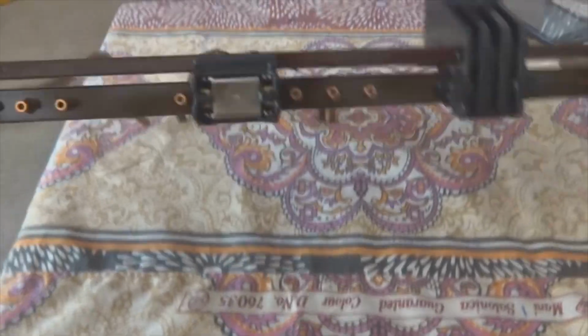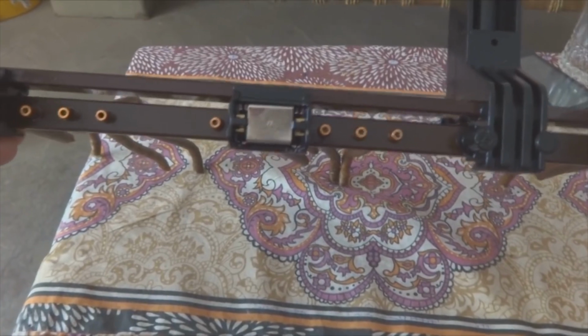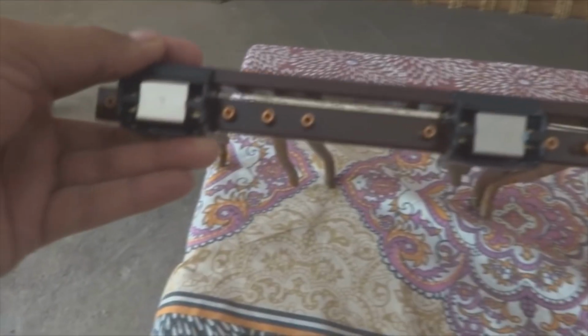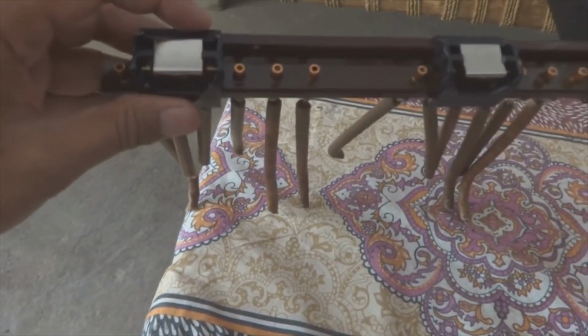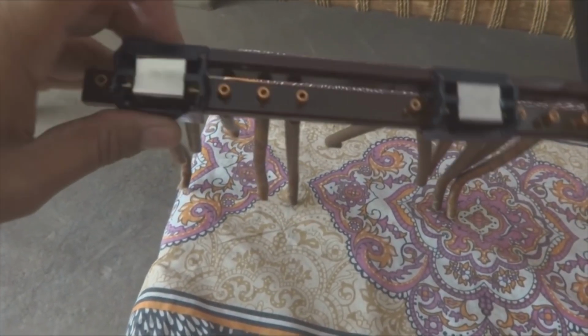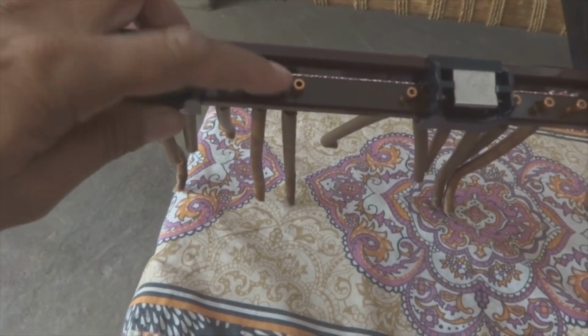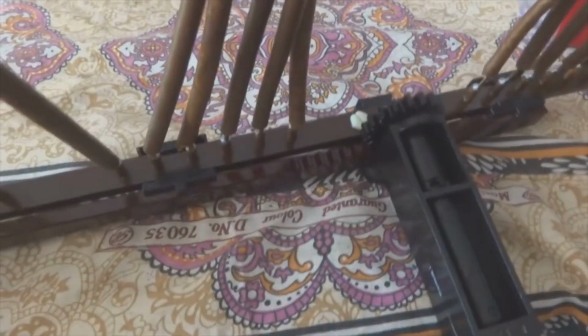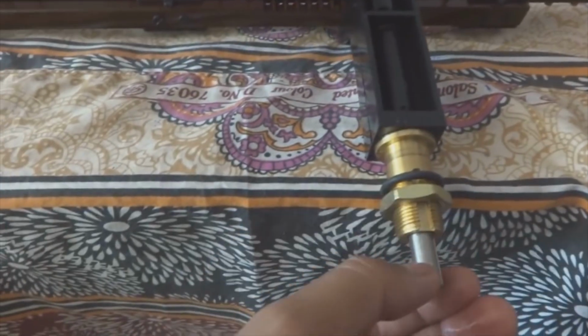So here is this device. You can see this is the tap changer. This is available inside each and every transformer. The tap changer is used because there are some tappings we are going to change. Here are the tappings, you can see these are the terminals, and here is the moving part. This moving part can be moved through this mechanism, the gearing mechanism, and this is outside of the transformer.